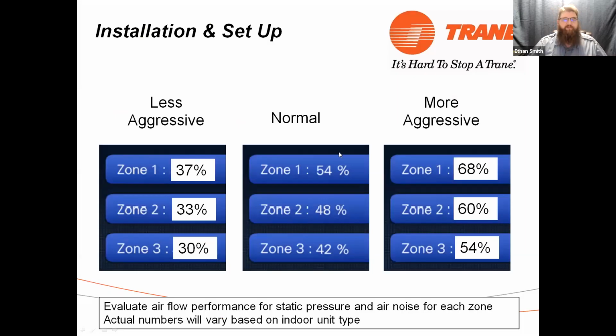And what it's going to do is go out and run that blower at 100%. Now, on a 4-zone system, this takes about 20 minutes. An 8-zone system is going to take about 45 minutes. Just kind of plan on that. It runs each damper to 3 positions, 25%, 50%, 75%, and then looks at the static pressure that's generated in the duct. So it does that for each zone. Then it starts combining zones and monitoring that. And it's just building that digital map for all the zones to see how much airflow they would tolerate.